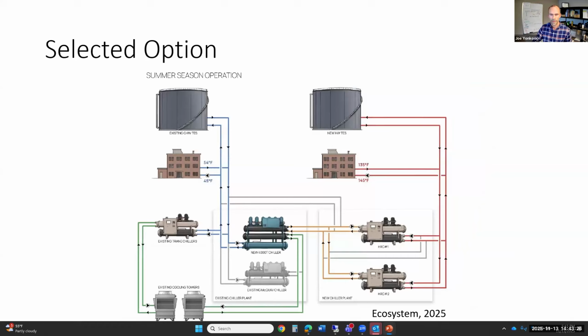Next slide. This is a simple flow diagram of what that equipment will look like. Again, existing chillers, and then it says one new 4,000-ton chiller. We actually asked them to split that into 2,000 tons, to help with redundancy and reliability. We didn't want a single point of failure for quite a large chunk of our cooling. We're getting two high side heat pumps in this phase, which will interface with the tank and the buildings. Next slide.